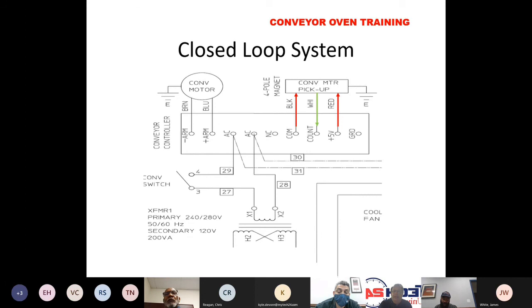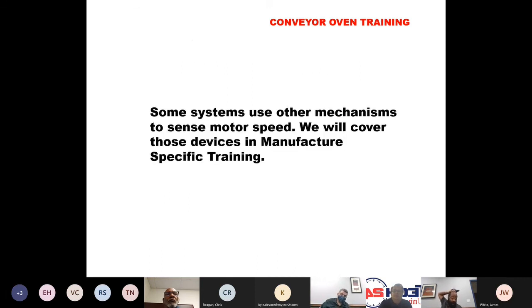The purpose of checking this is really, number one, to make sure you have the output voltage from the controller if your oven is not controlling speed properly, and then to make sure you're getting return voltage. A lot of times if we're seeing the +5, but we're not seeing our common and count return voltage, it may simply be that our sensor is too far away from the magnet. In most applications, the sensor should be no more than the thickness of a business card away from the magnet. Some systems use other mechanisms to sense motor speed, but we'll cover those when we do manufacturer-specific training.